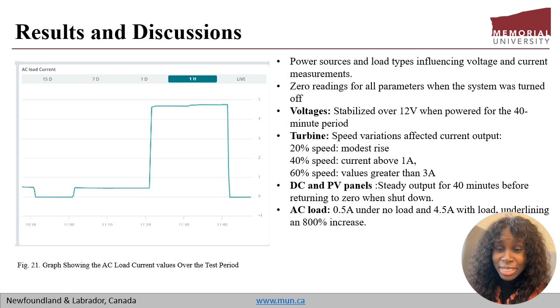Now, the key findings we picked up on this project: IoT SCADA dramatically improves system performance and reliability, because when we included the buzzer, we are able to detect when the voltage drops below a predetermined value, and this prevents unexpected shutdown. So what it does is it will now beep to alert the operator in the room that the voltages are dropping, especially from the PV panel, so that same signal can be used to bring on an alternate power source, so we don't have to face an interrupted supply.